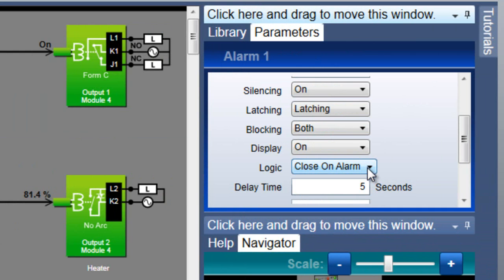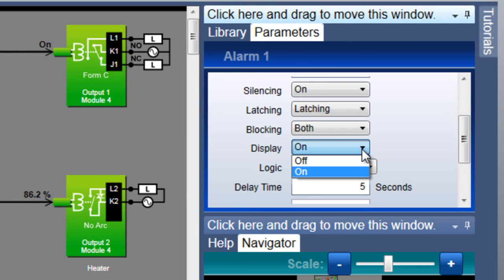The display setting determines whether or not the alarm shows up in the user interface when it occurs. If you want to use the alarm block to perform a task that doesn't require any operator intervention and you don't want any alarm message displayed on the user interface, set display to off. This would normally be used with a non-latching alarm since no one will be notified to clear it.